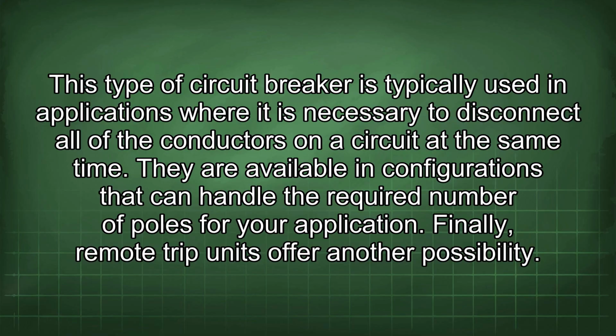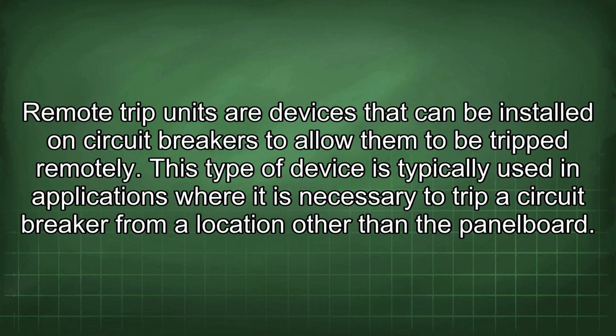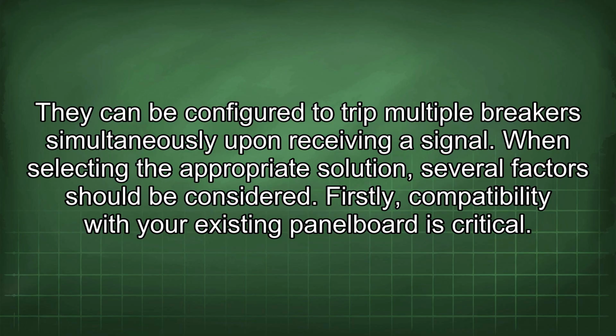Finally, remote trip units offer another possibility. Remote trip units are devices that can be installed on circuit breakers to allow them to be tripped remotely. This type of device is typically used in applications where it is necessary to trip a circuit breaker from a location other than the panel board. They can be configured to trip multiple breakers simultaneously upon receiving a signal.